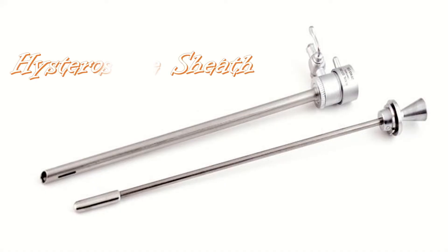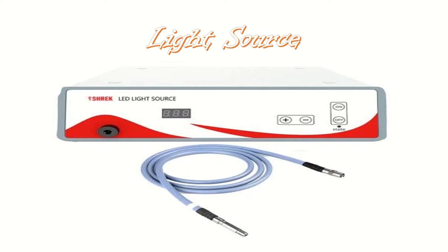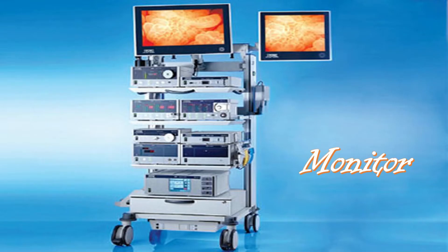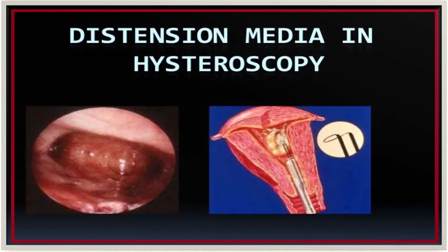The second part is the hysteroscope sheath, consisting of an inner sheath and outer sheath with obturator. The next part is the camera and stack system — the hysteroscopic image is visualized on a monitor with the help of a camera connected to a camera drive unit. The light source requires a minimum power of 150 watts to obtain a clear image. Other parts include the monitor and image rotating equipment, and finally the distension medium.